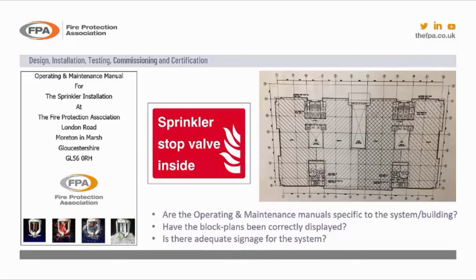This information is very important, and many sprinkler inspections that I've witnessed have not got this information, and you find it very hard to understand what the system is doing and where its key components are. If, for an emergency, you needed to isolate the system, you would refer to the block plan and find out where there's a fire, what zone it's on, and where to isolate it. And also signage. So when the building's up and running, this should always be there. We should know where all the critical components are.